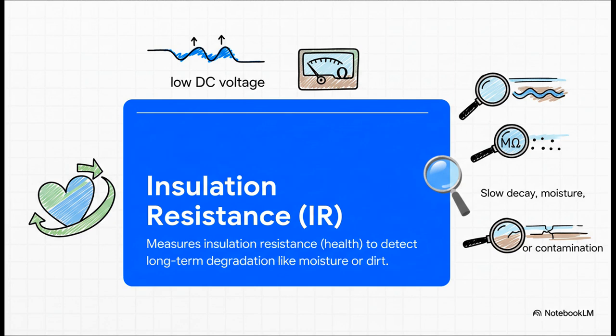You should think of this one like a health checkup. It's not trying to push the insulation to its breaking point. Instead, it just applies a steady, pretty low DC voltage to measure the quality of the insulation. It gives you an actual number, a value in megaohms. What it's really looking for is slow decay, maybe a little moisture, or some contamination.